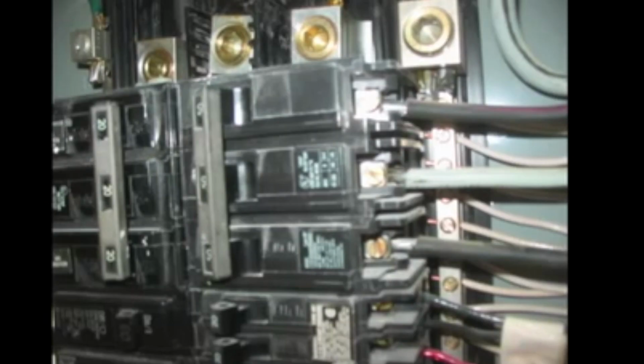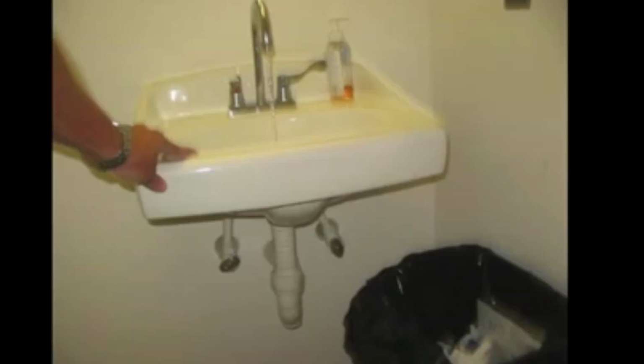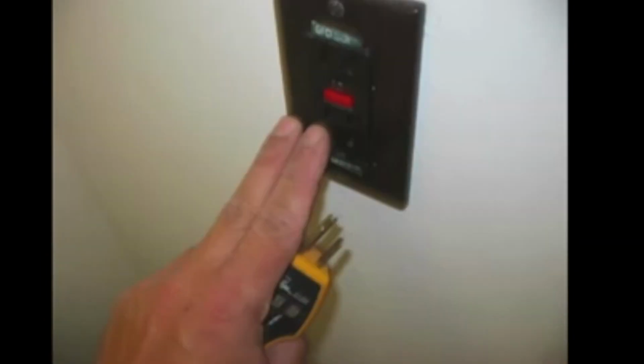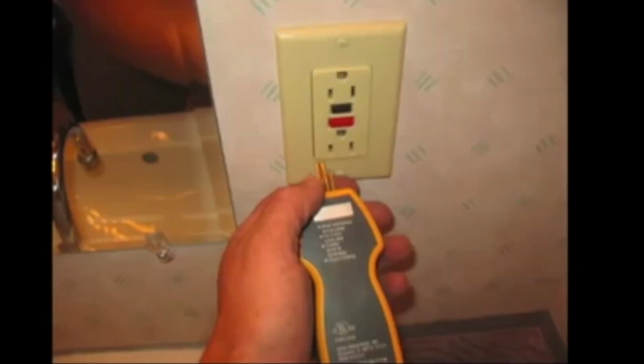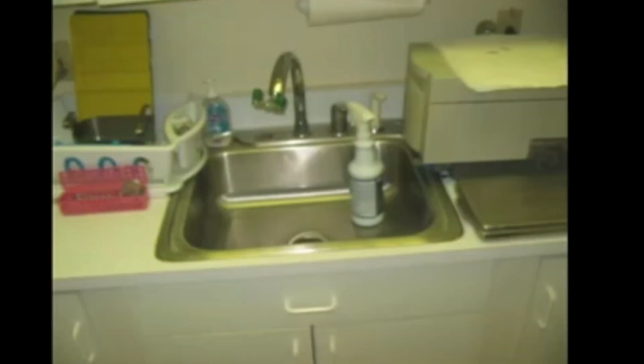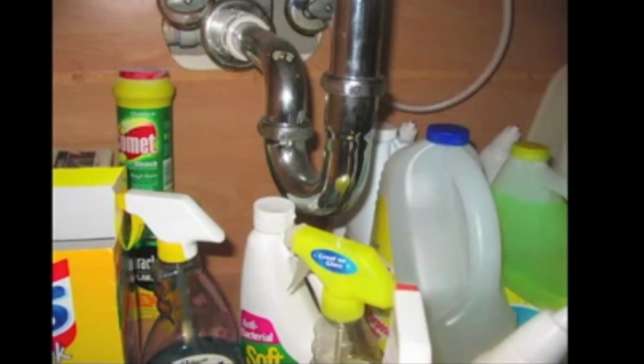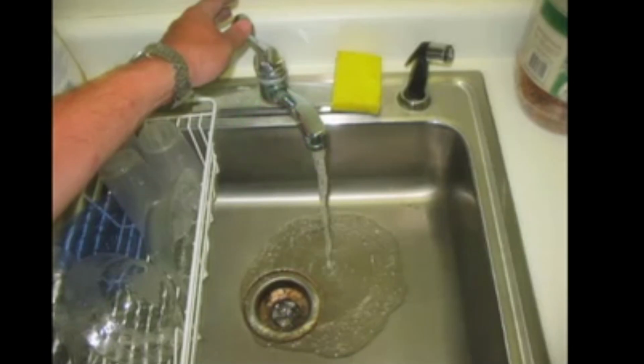And now I'm to the interior, doing the bathrooms, kitchenettes, just like a residential, flushing toilets, running sinks, testing ground faults, looking for leaks, hot and cold water, wondering where the fan is exhausting, and the bathroom fans are exhausting right into the attic space. Kitchenettes, a lot of sinks in a commercial building, used for hand washing or whatever the facility is used for. Just look for hot and cold water.